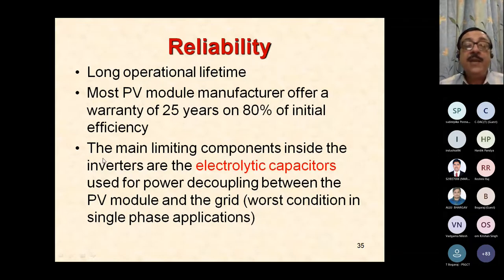Okay, the main limiting components inside the inverters, that's the second supplementing part, are the electrolytic capacitors, which are used for power decoupling between the PV module and the grid. These capacitors restrict the lifetime that you can expect, because after some years of operation, depending on the temperature to which they are subjected, the capacitors degrade and ultimately there is a short circuit in the dielectric inside and they fail. Therefore, if they fail, the entire inverter system fails.